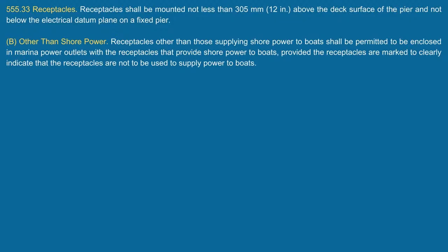This is where they come in and say other than shore power. Going back, it says: receptacles other than those supplying shore power to boats shall be permitted to be enclosed in marina power outlets with the receptacles that provide shore power to boats, provided the receptacles are marked to clearly indicate they are not to be used to supply power to boats. Nice - how much more clear can this be? It's specifically telling you, receptacles. Yeah, and the reason they're saying receptacles is because the receptacles are being mounted in the receptacle outlet, not at the end of the equipment.